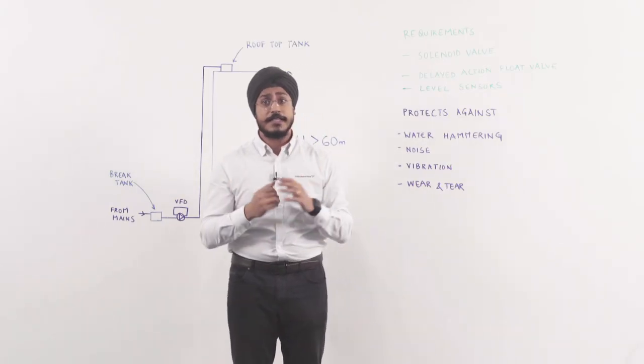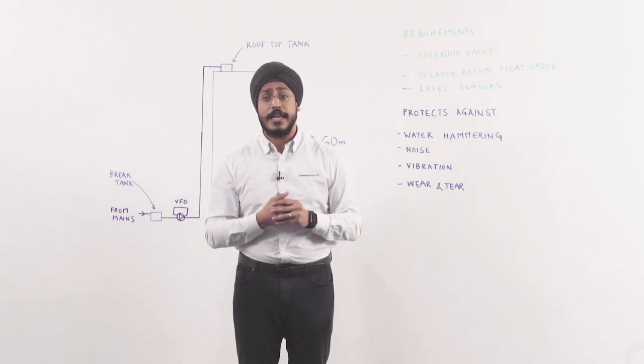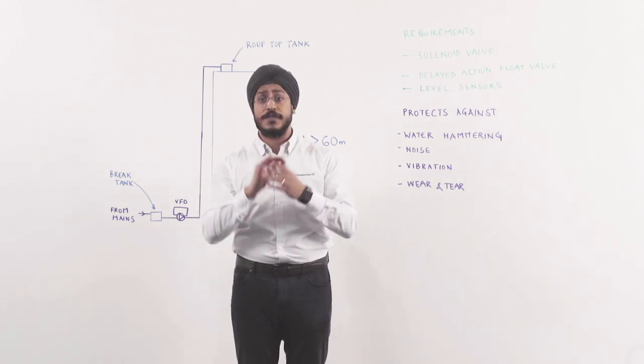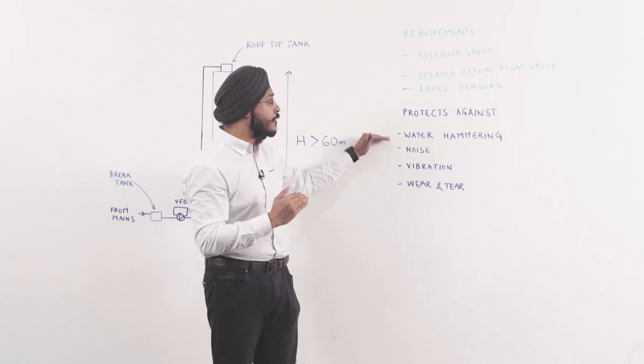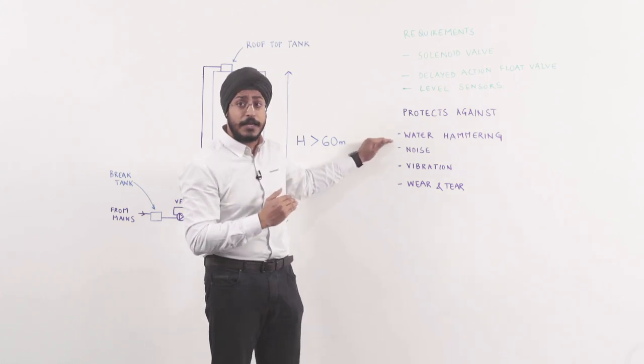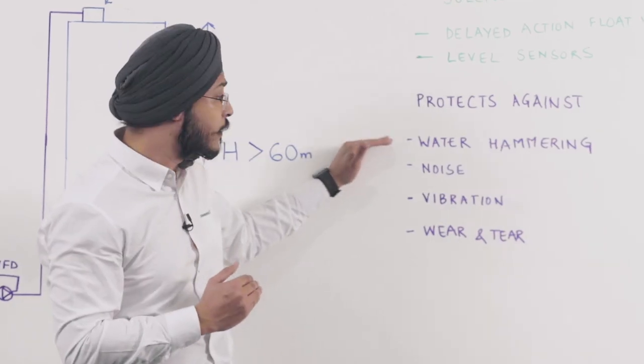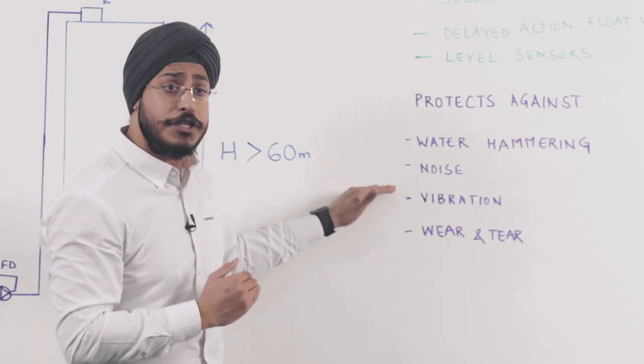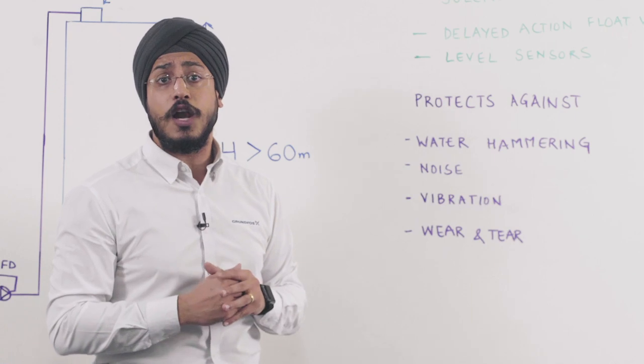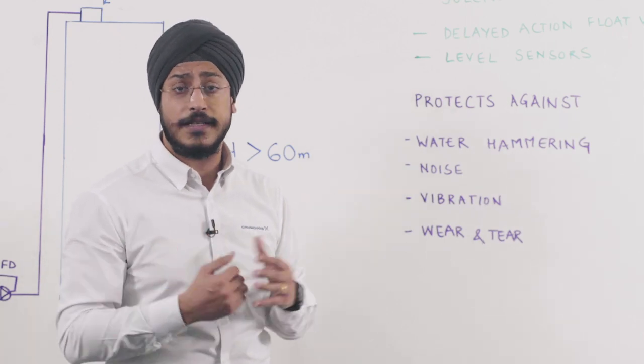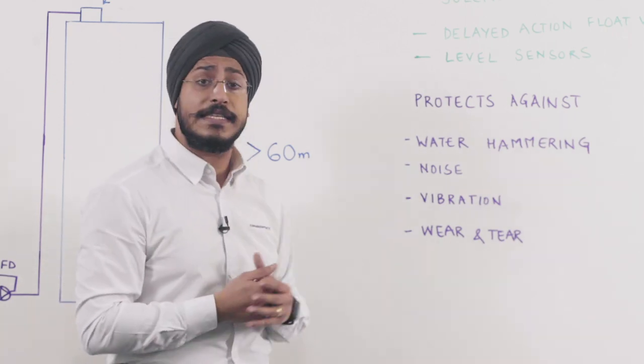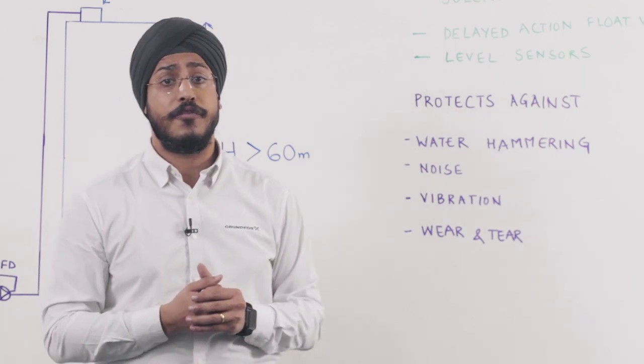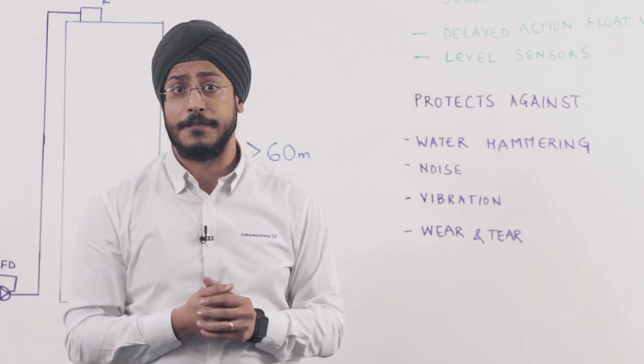Just to conclude, for any buildings above 60 meters, we recommend the use of variable speed water transfer systems as they help in reducing and protecting the system against water hammering, noise from the flow of water in the pipes, vibrations that actually cause a lot of damage to all the joints in the system, as well as the excessive wear and tear that comes from the sudden ramp up and sudden ramp down.